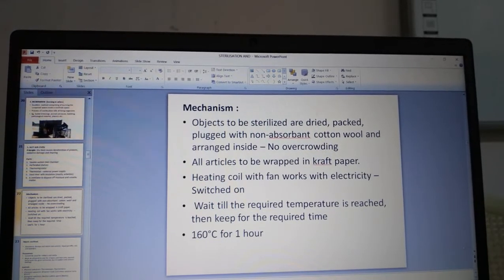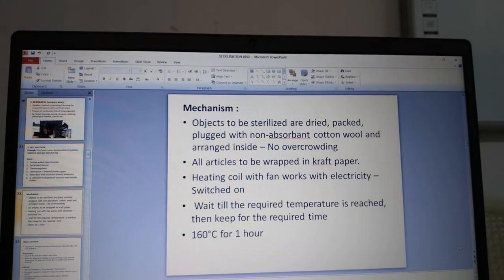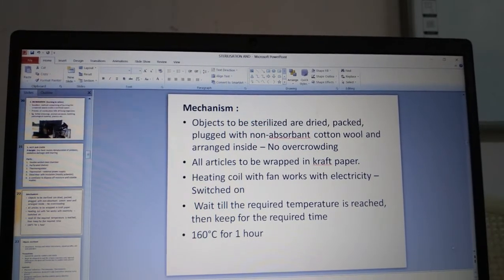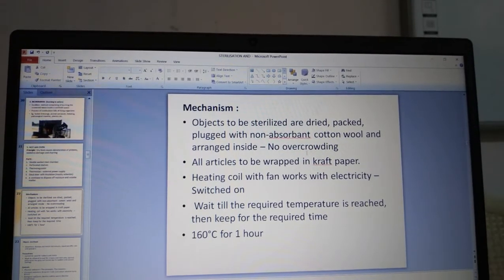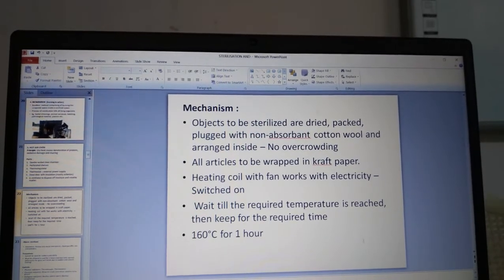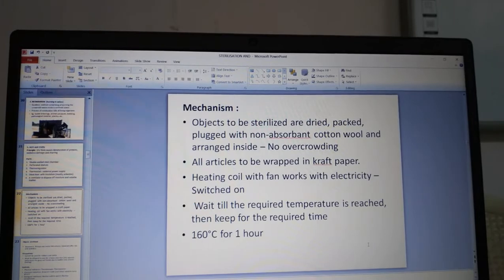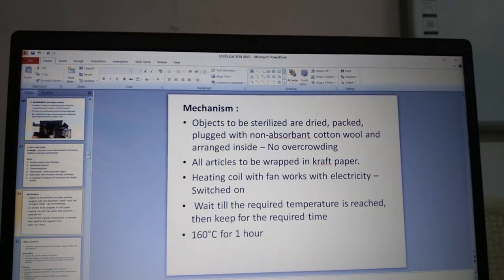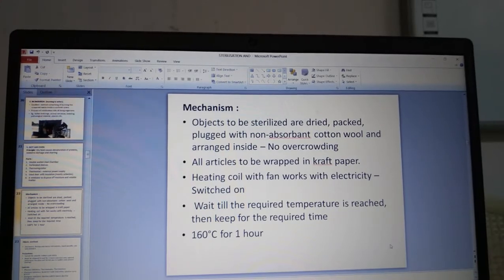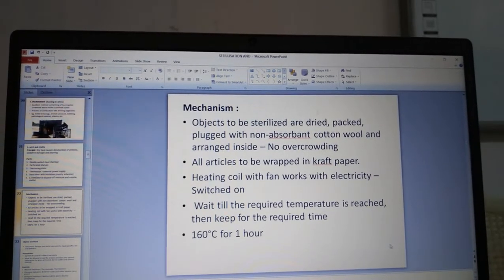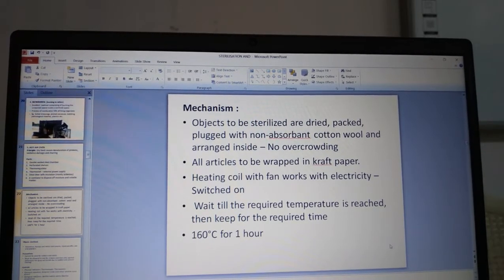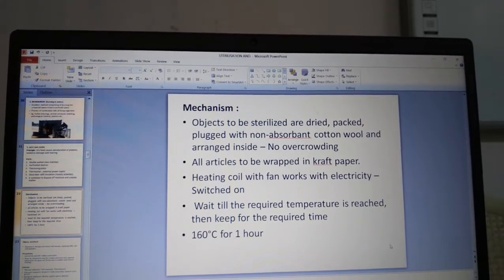The objects to be sterilized are dried, packed and plugged with non-absorbent cotton wool, and arranged on the perforated shelves. They should not be overcrowded as there must be free circulation of hot air inside the oven. All articles are to be wrapped in kraft paper. The heating coil with fan is switched on, and you wait until the required temperature is reached — mostly 160°C for one hour.